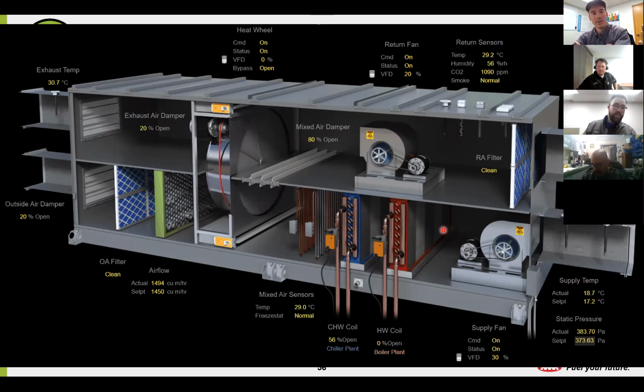At the same time, you'll notice that the outside air damper was 20% open. So there is some air being pulled in through the outside air here, and that's going to get filtered. We want to filter the air coming into the space. It's going to pass through these little cones here, which take out a lot of the turbulence. And then that passes through this heat recovery wheel. Because we exhausted some air and recovered heat, that heat we're bringing back in, we'll pick some of that up. This is maybe not the best situation for it because we're cooling, but the principle is still the same. We just want to reclaim heat.